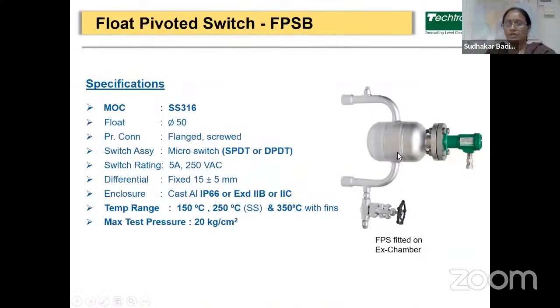So on the right side, you can see the float pivoted switch, which is mounted with the external chamber. Material is available in SS316. The switch assembly will be available in SPDT or DPDT form. Enclosures can be IP66 or X-proof 2B or 2C. Then it is suitable for temperature range of up to 150 degrees Celsius, 250 degrees Celsius, or 350 degrees Celsius. Three options are there. Then it is suitable for maximum test pressure of 20 kg per centimeter square.